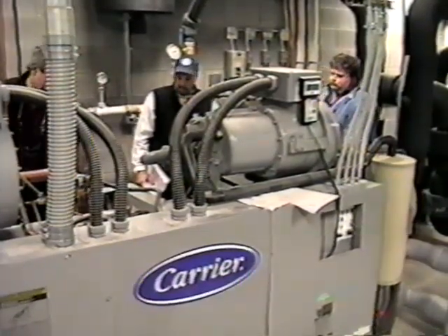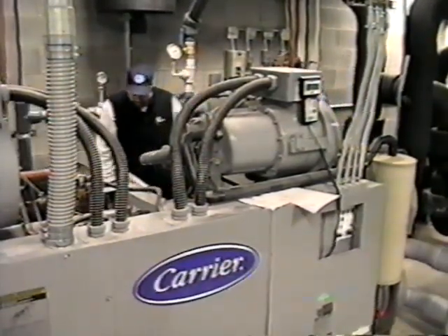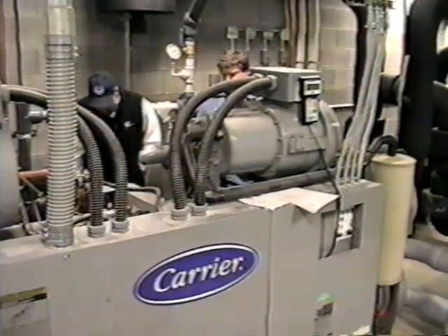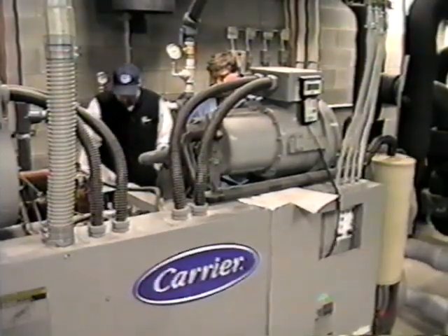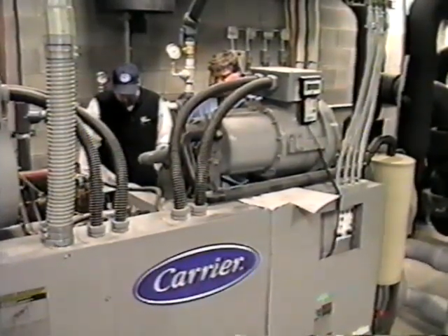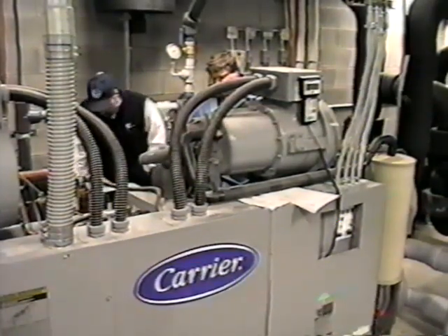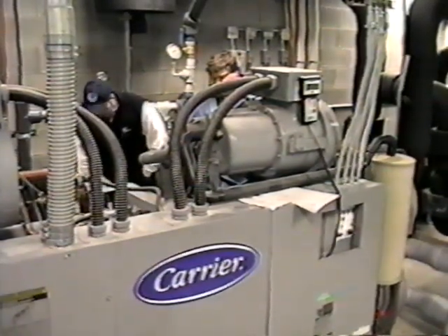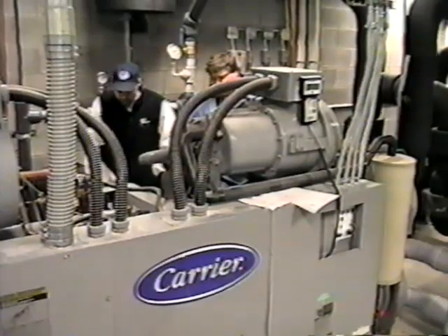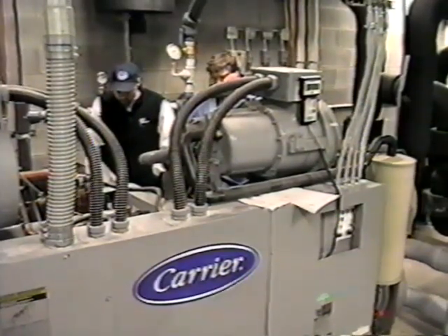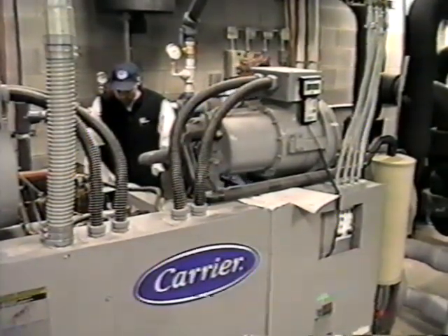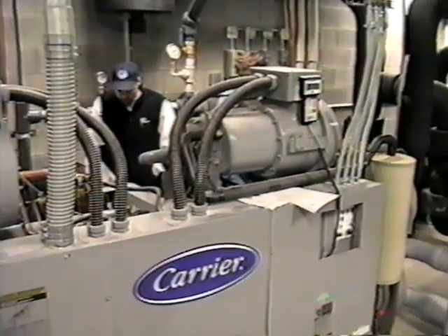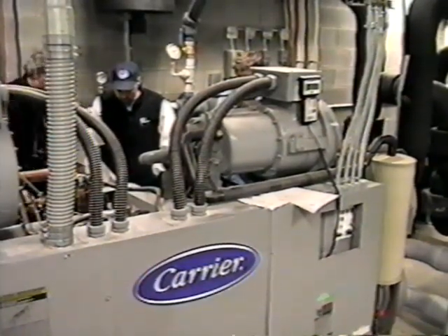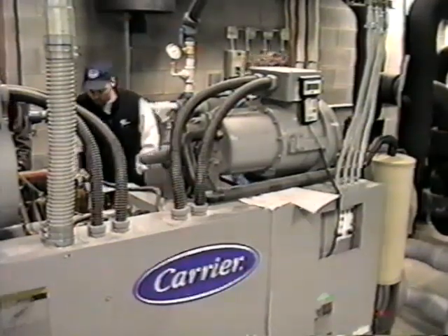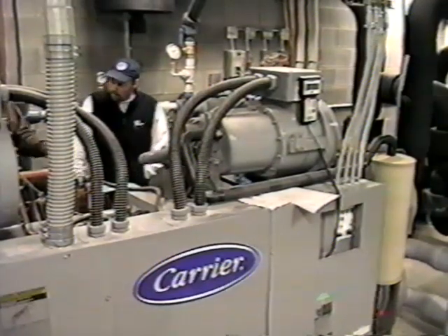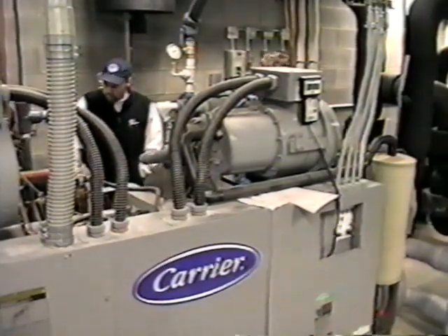There is an oil level indicator down here. You should see the oil level in one of these two sight glasses, and it's going to fluctuate. Sometimes you can see it at a natural level, sometimes you can't. This switch monitors that oil level. If the oil level is low, it'll shut it down. Like I said, it's duplication; one circuit is exactly the same as the other.